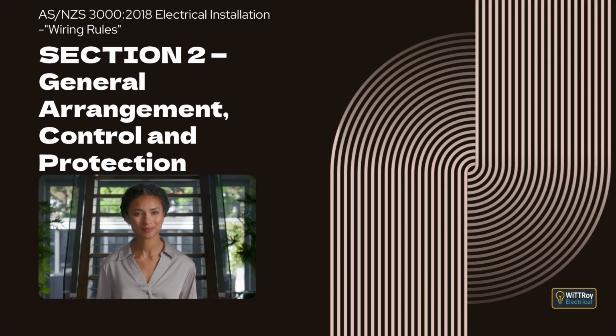Isolation is the function that fully separates the equipment from the supply. Emergency switching is for situations where the supply must be cut off quickly to remove danger. Mechanical maintenance switching makes equipment safe for physical work. Functional control is everyday switching used to run equipment. If one device performs more than one of these functions, it must still meet the rules for each function it performs.